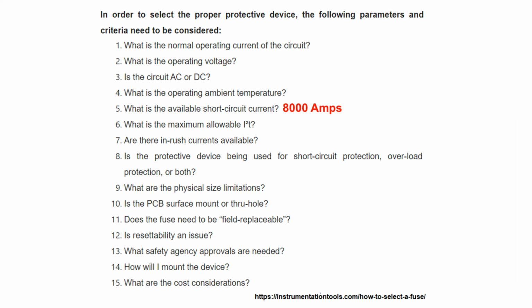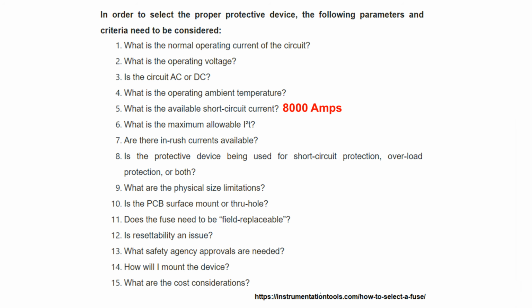So now, for those who don't know, why did I say the available short circuit current is 8,000 amps? If there's an bolted short circuit, which means the line conductor is directly connected to the grounded conductor, the transformer out on the utility pole can deliver 8,000 amps through the circuit until an overcurrent protective device, such as a fuse or circuit breaker, opens up and stops the current flow. If you look at a circuit breaker or fuse, you'll find an AIC rating. That's a current interrupting capacity.